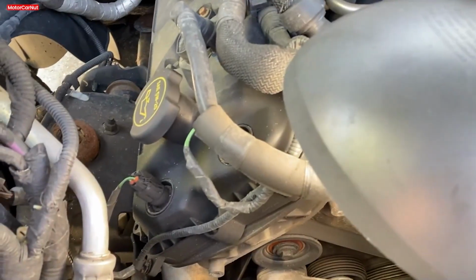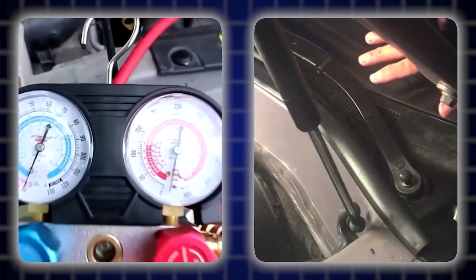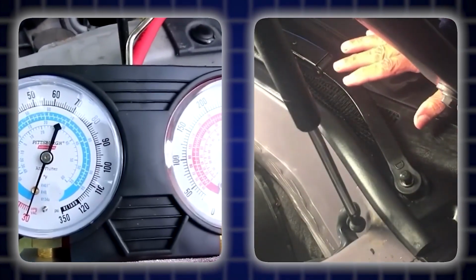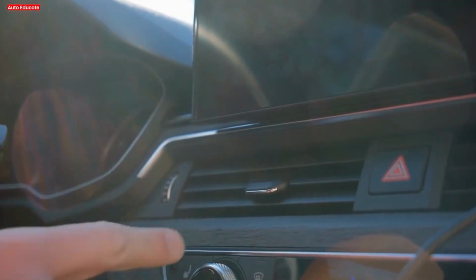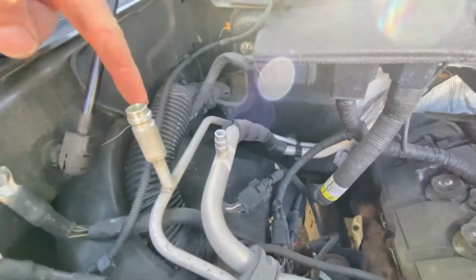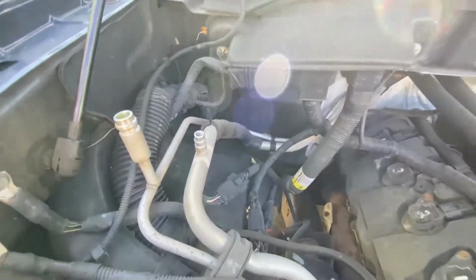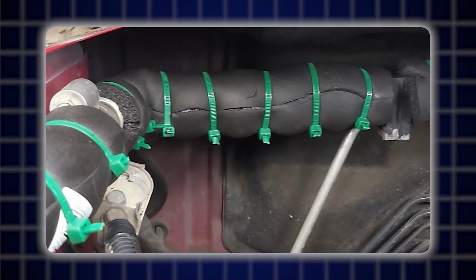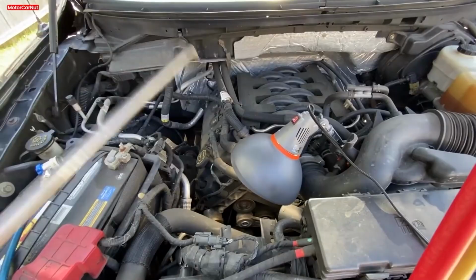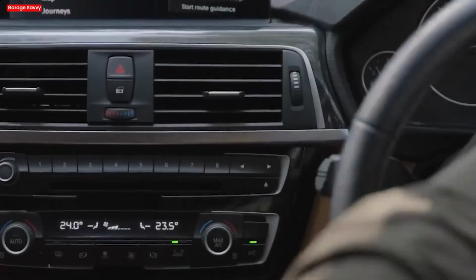If that line absorbs heat, the refrigerant feeding your evaporator next cycle starts warmer than it needs to. The fix is a cheap stealth upgrade: wrap the low side line with closed-cell foam pipe insulation and secure it with zip ties. Avoid the high-pressure, hot line. The effect is incremental, but real.